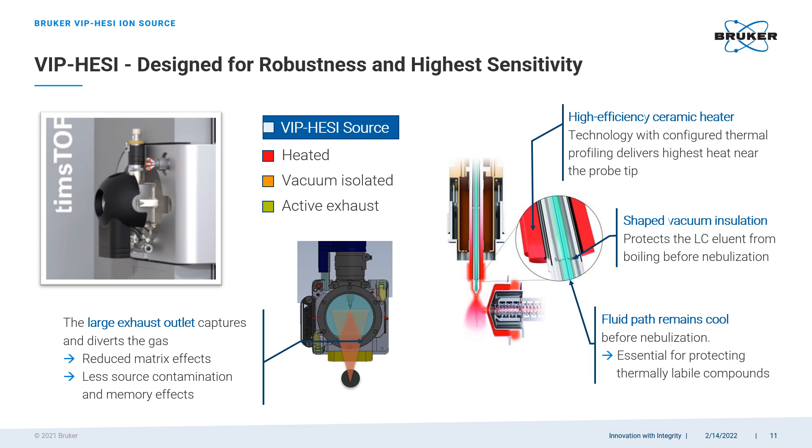One of the most recent technological improvements from Bruker is the new heated vacuum-isolated electrospray ion source with active exhaust, or VIP-HESI for short. Historically, nominal-mass triple quadrupole mass spectrometers have reigned supreme in targeted analysis because of their unsurpassed sensitivity. The new VIP-HESI source brings Bruker's high-resolution instruments to a similar level by boosting their sensitivity by an order of magnitude. On top of that, the VIP-HESI source reduces matrix effects and contamination buildup by carefully managing the gas flow inside the source, making it both very sensitive and extremely robust.